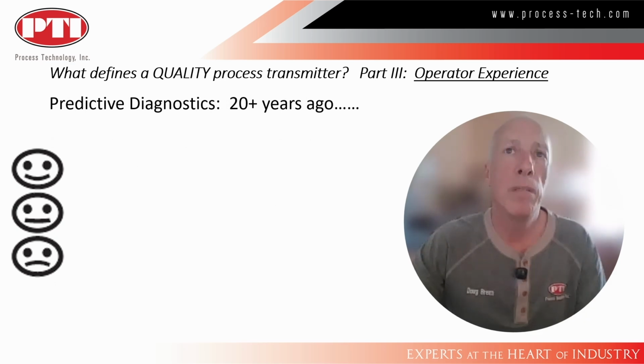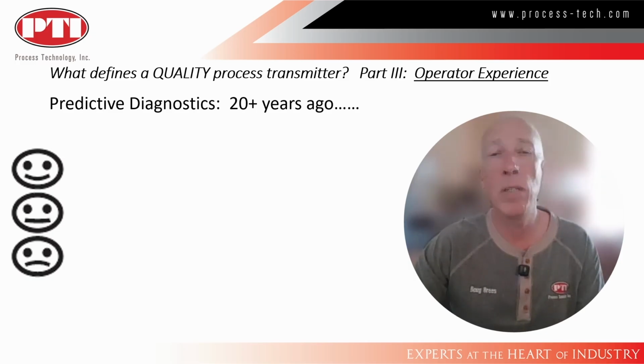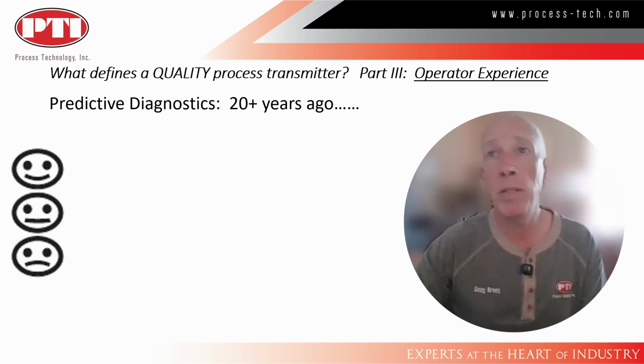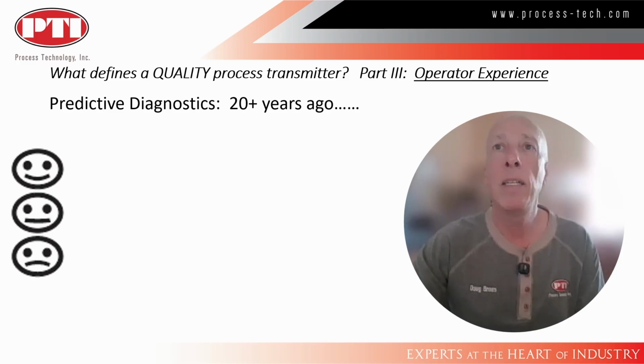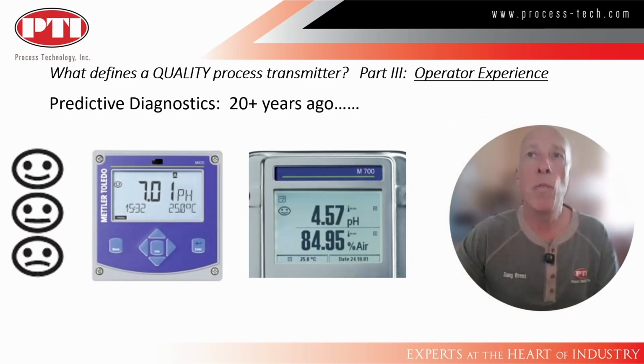Just after 9/11, Mettler introduced a revolutionary graphical diagnostic feature, the three faces. Smile means it's all good, neutral, it's trending away from good, and sad, I've got issues. Mettler promoted this as if it's smiling, you keep on walking. Otherwise, you need to stop and do something. It really wasn't always clear what you were supposed to do, or specifically what was the issue. Do you clean the sensor? Was the glass cracked? Reference junction clogged? Needs calibration, etc. But still, 20 years ago, this was a huge improvement.